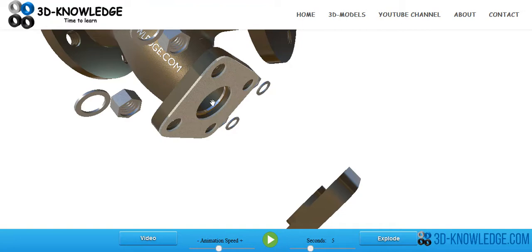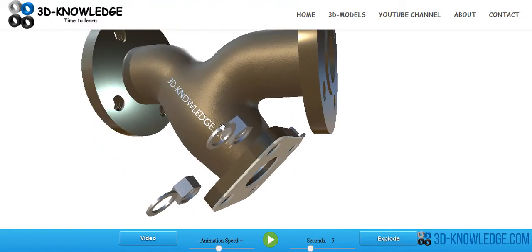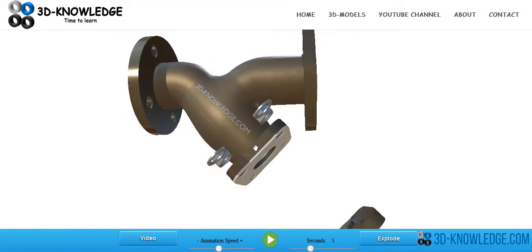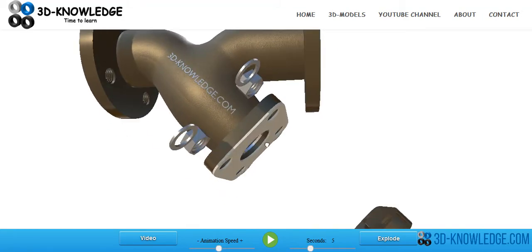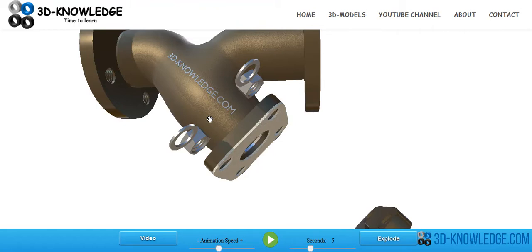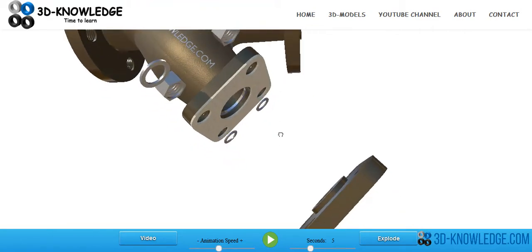If you are doing this for a freshwater system though, just beware that whatever you're using, especially if it's a grease of some sort, this could potentially be drinking water, and you don't really want to apply something like oil or anything that's carcinogenic to the gasket, which is then potentially going to leak out into the freshwater system and people are going to drink it. So just keep that in mind. There are biological products that you can buy which will also serve as good greasing medium.